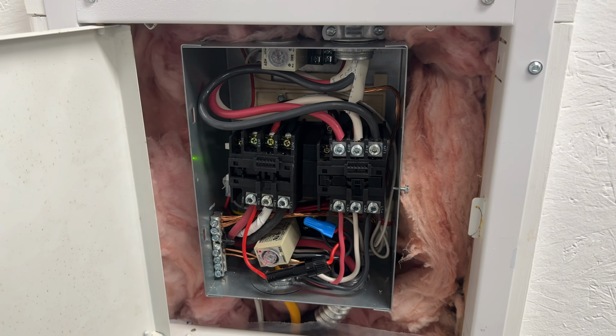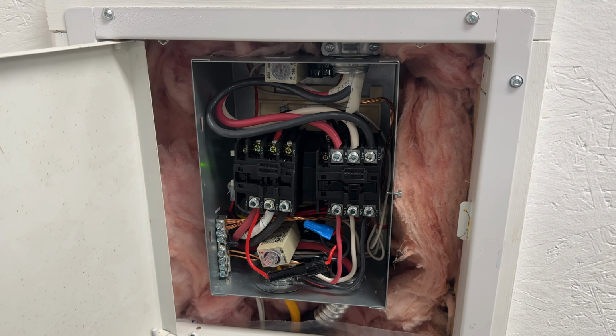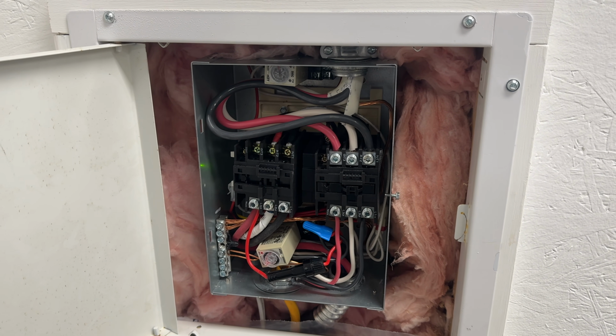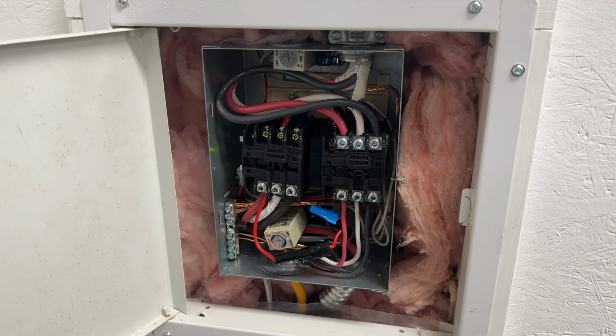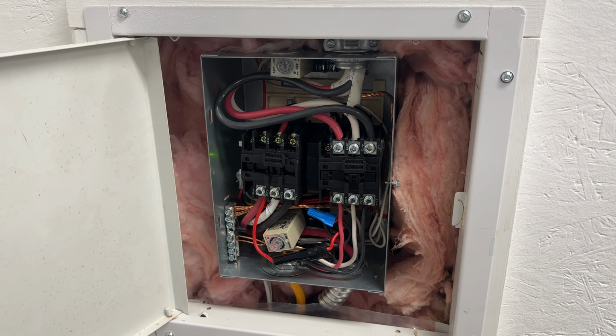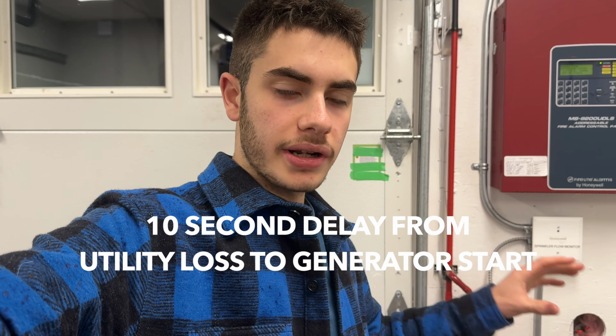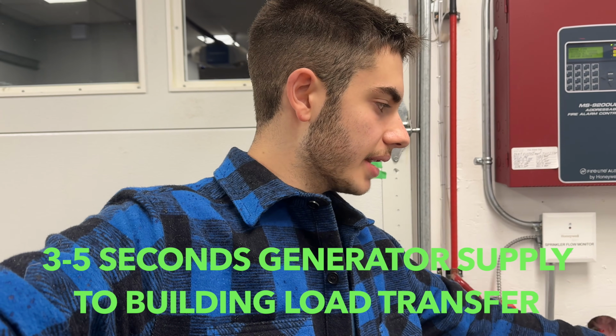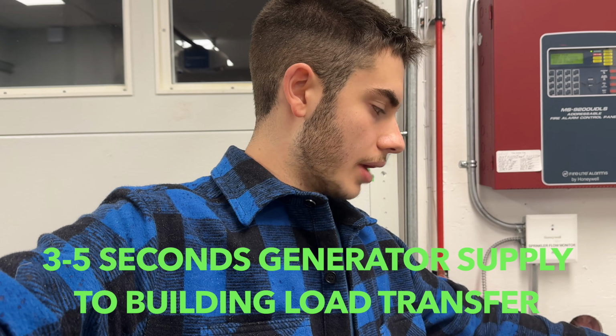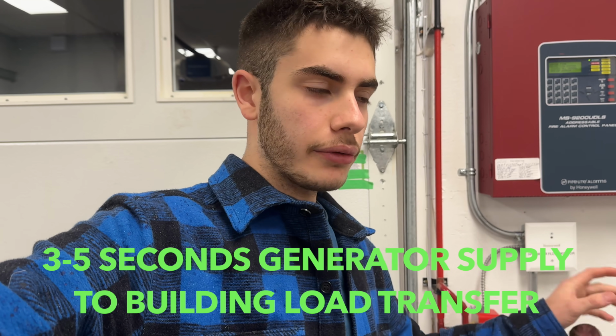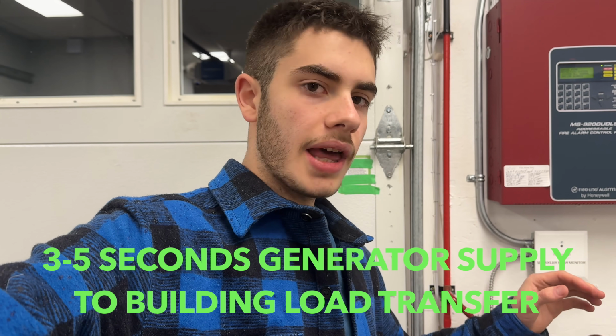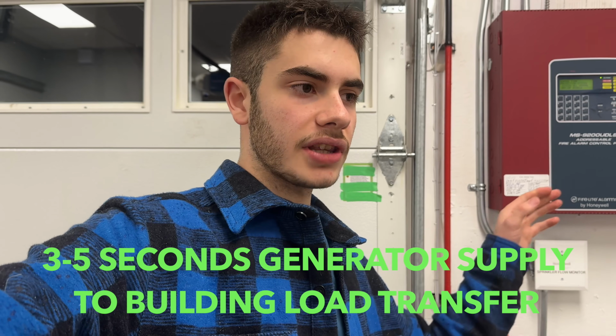I do have various time delayed relays and different time delays that are built into the program of the generator controller, so I will give a brief sequence of events. Once utility power goes out, the generator controller will wait 10 seconds before starting the generator. Once the generator is started, the time delay relay in the transfer switch will wait an additional 3 or 4 seconds to make sure that power is stable before transferring the building's load.